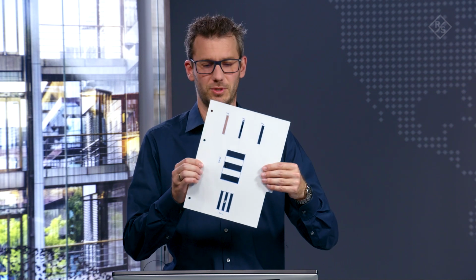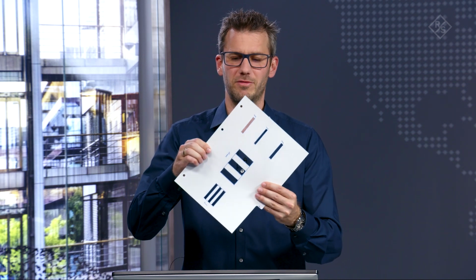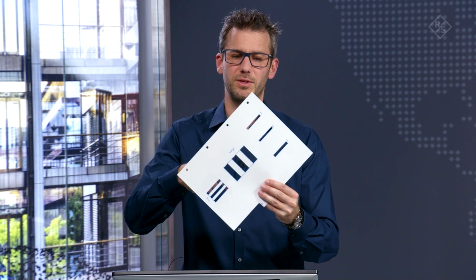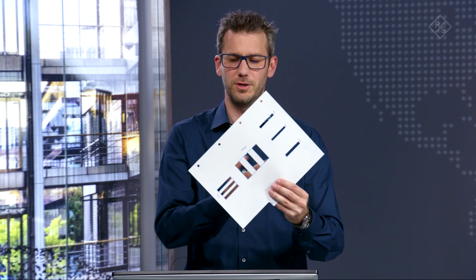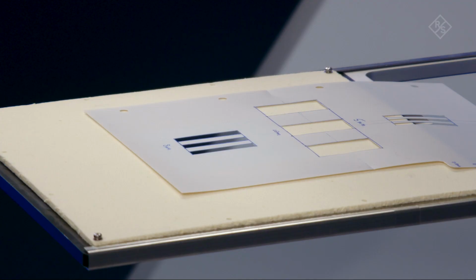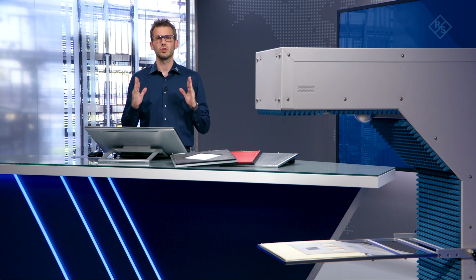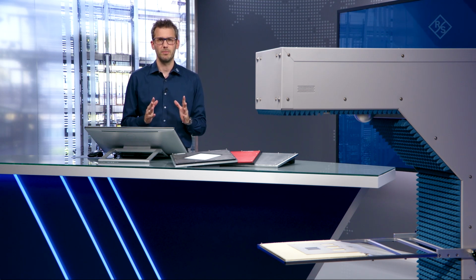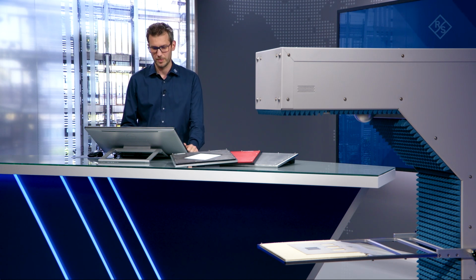Therefore, we have prepared different foils with different cutouts. In this case, I have a foil with a cutout of 60 millimeters in the middle and different cutouts here on the left-hand side and on the right-hand side. There's another one of those foils inside the instrument. The foils have a thickness of about 190 micrometers and they cause a phase change of about 14 degrees. We want to see how small we can make the cutouts in order to still be able to distinguish between them in the QAR50's image.